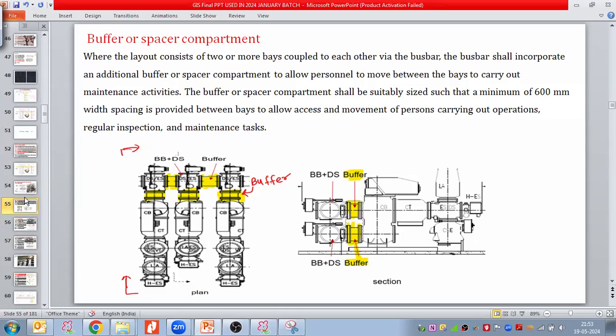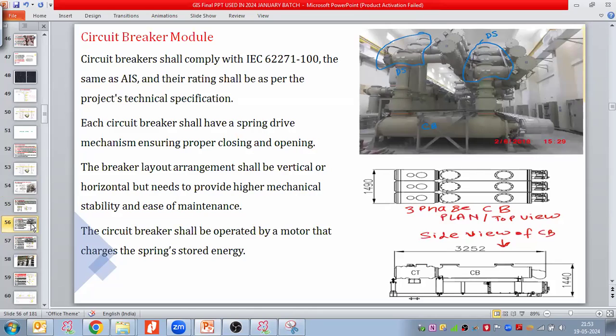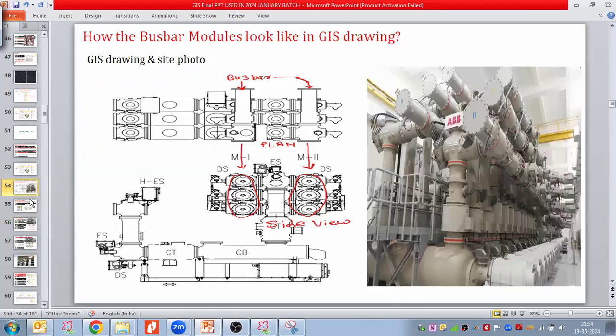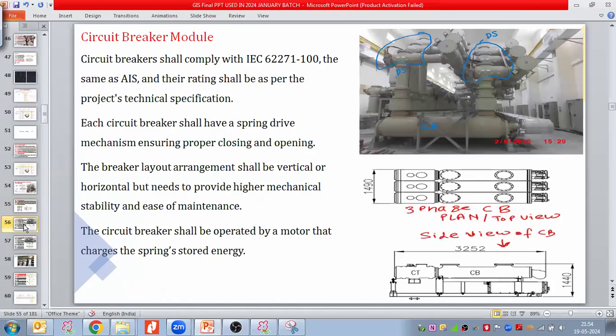Now coming to the next equipment module. After the bus bar, let us take up the breaker module. How does the breaker module look in the drawing and in the site photo, just for comparison purposes? We discussed the bus bar conductor sizing, that the material and size are provided by the manufacturer. Now coming to the next equipment, which is the breaker equipment.